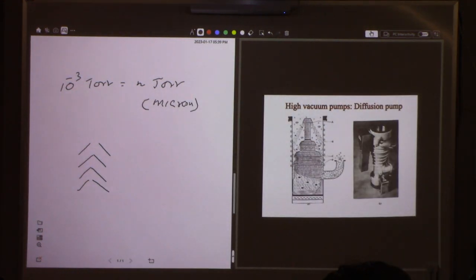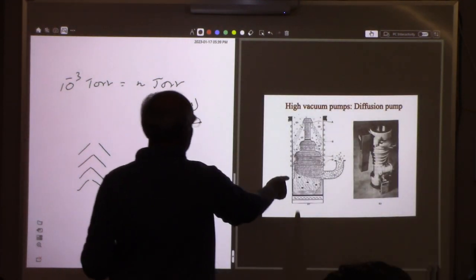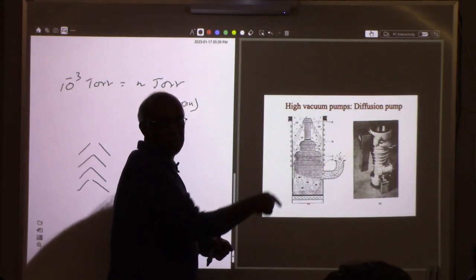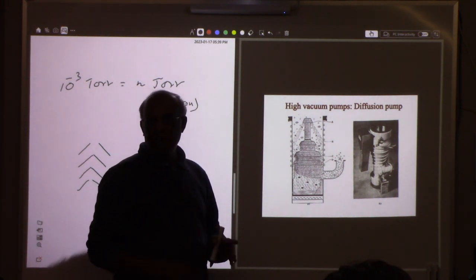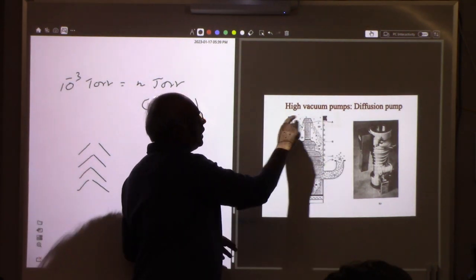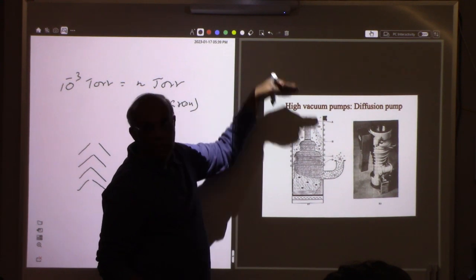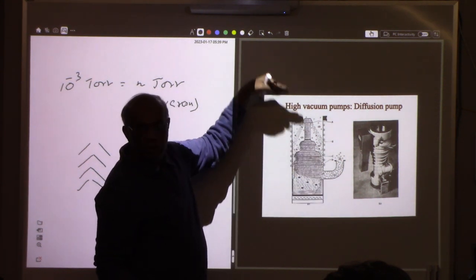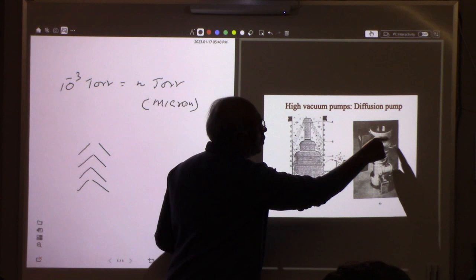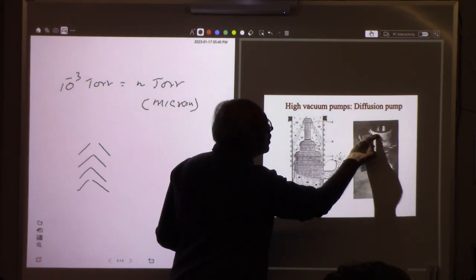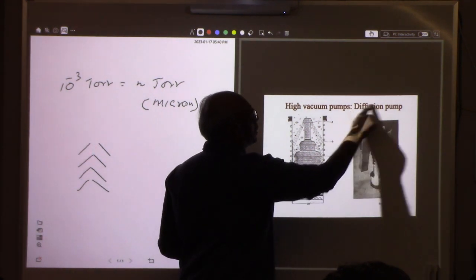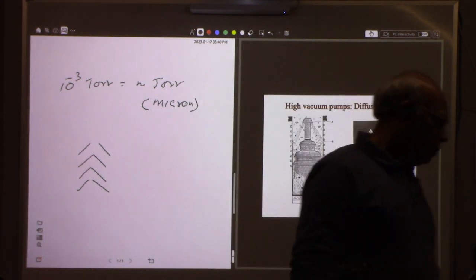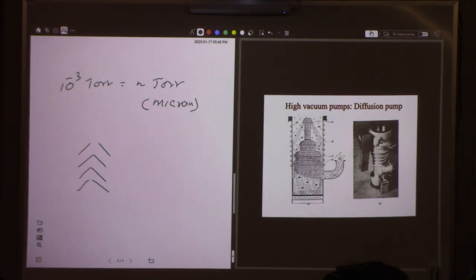That's the basic principle of a diffusion pump. The only problem is that these oil vapors can backstream onto your system, right? That's not good, so your system becomes kind of dirty. For that reason, what people do is they put some kind of liquid nitrogen buffer here. So the oil will condense, so it will not get to your chamber. Otherwise, this high vapor pressure oil can get to the system. So any diffusion pump should have that liquid nitrogen trap, which should be coming after this one.